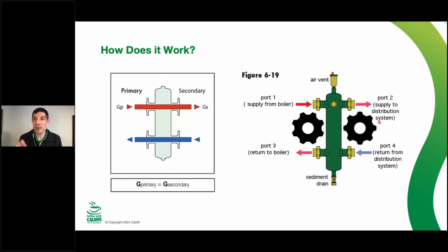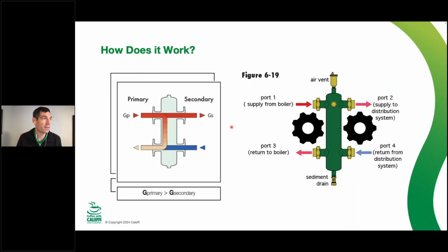This is the 0.0001% of the cases in a modern hydronic system that you'd have exactly the same GPM, same head loss, same flow rate on both sides. The other 99.9 whatever, math I just stated there, percent of the time, you're going to have something more like this, where you have a higher flow rate either on the left side or the right side. So we'll say this is a boiler that started up, we're moving 10 GPM on the left side, but we only have one microzone open on the right side.